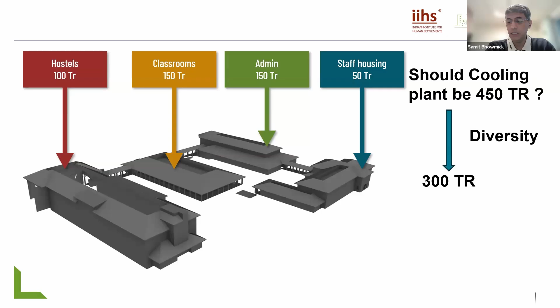Now, there is no thumb rule for this diversity. What I would recommend, and something you should work toward, is a load profile, which gives you an hourly trend, a seasonal trend, or maybe an annual trend as well. On this, you can plot out the coincident cooling loads from different buildings. In this particular example, you see that it's 316. Like in the previous slide, we roughly arrived at 300 tons. A more accurate analysis can bring you to a more reasonable figure of overall cooling load.